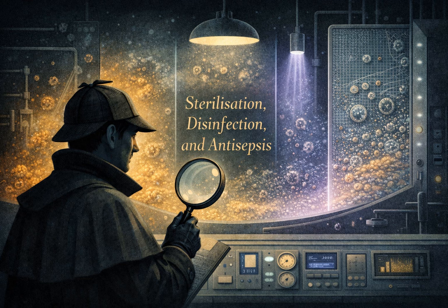So the logic is, if the autoclave cycle killed this heat-loving superspore, then it definitely killed any of the wimpy pathogens that might have been on the instruments. That's the logic exactly. You put a little vial containing these spores in the center of the autoclave load, the hardest place for the steam to reach. After the cycle, you take it out and try to culture the spores in the lab. If they don't grow, the load is certified sterile. If they do grow, you have a big problem. You have to recall and re-sterilize everything. That is such a clever, elegant system. It's the only way to be truly sure you've achieved that 1 in a million standard.